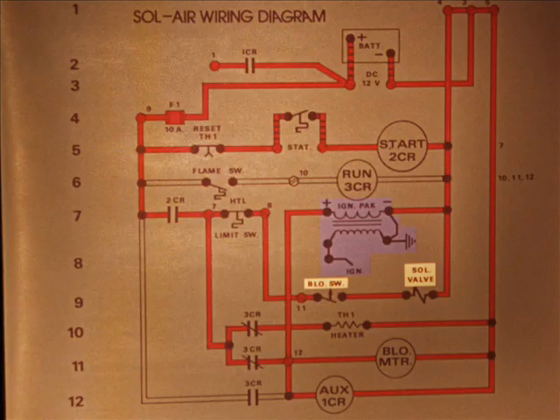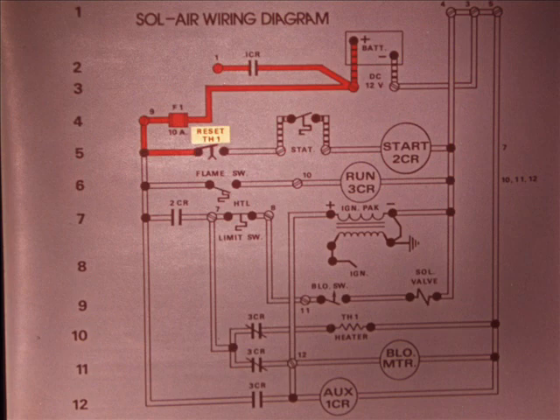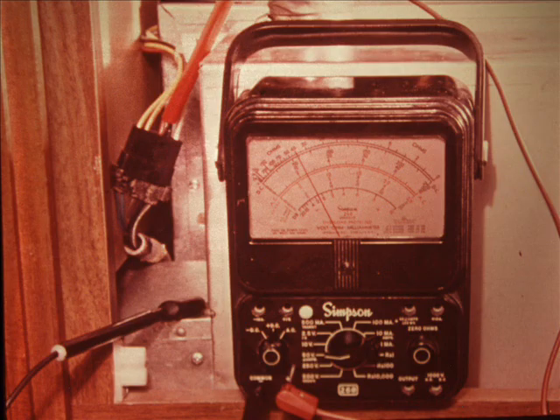Here's why. When the furnace first starts up, the blower has to get up to speed in order to close the contacts on a centrifugal switch, which opens the gas valve by energizing a solenoid. The thermal relay heater is de-energized when the fan switch is energized. But if the voltage is low, the gas won't come on, and in a few seconds the thermal relay will pop the reset and shut everything down. So, if the blower comes on momentarily but the furnace doesn't fire, always check the voltage source first.